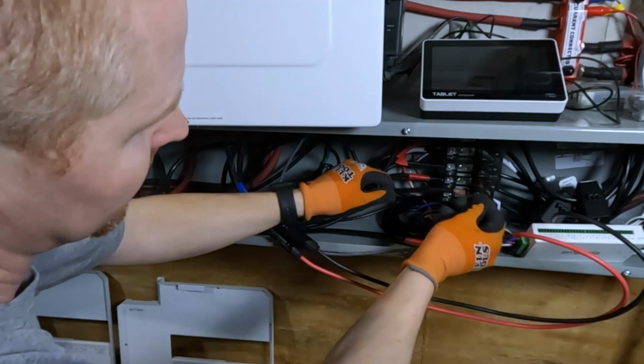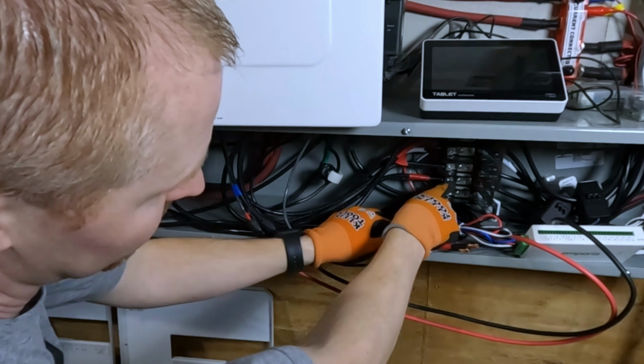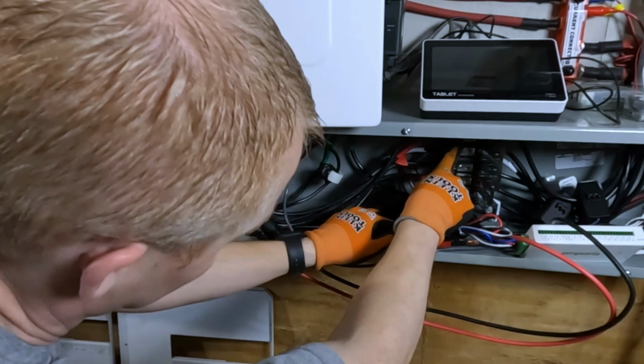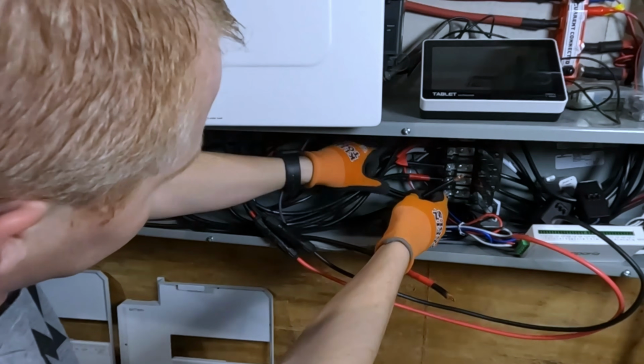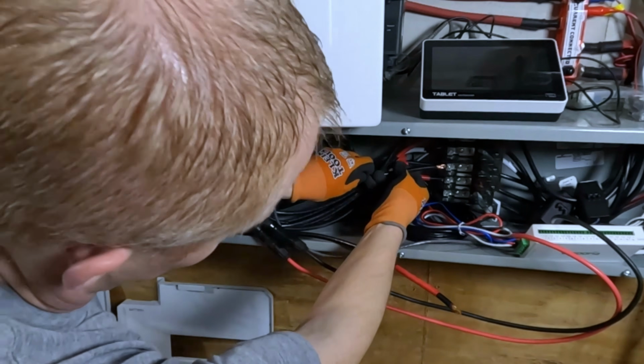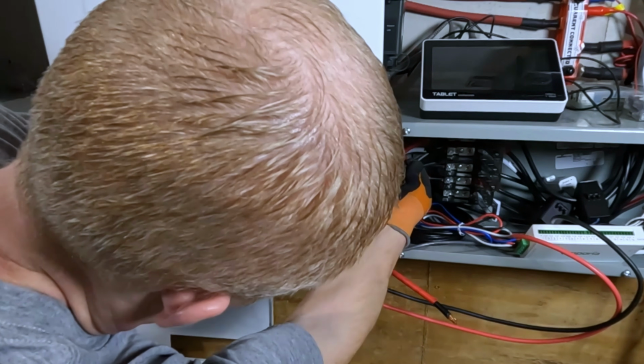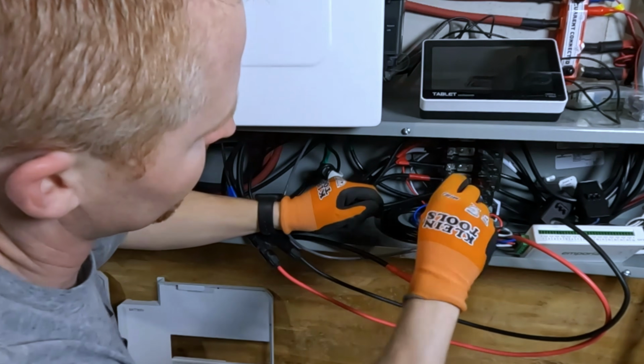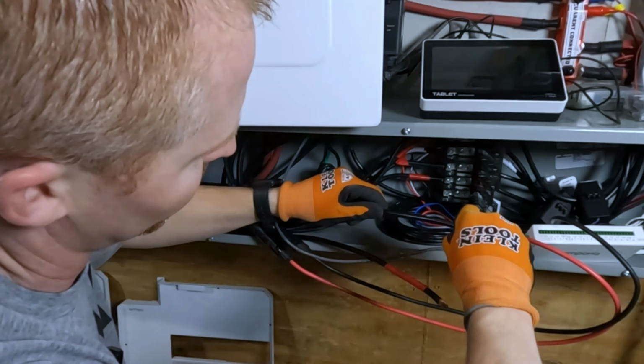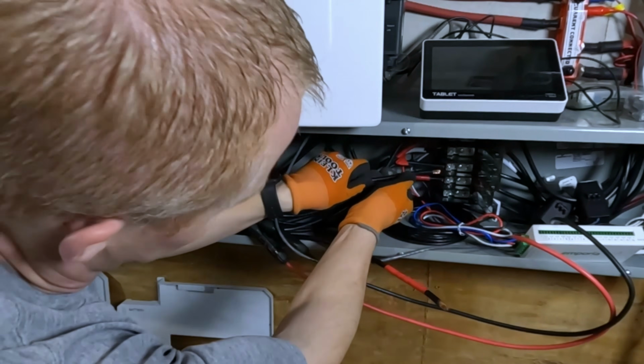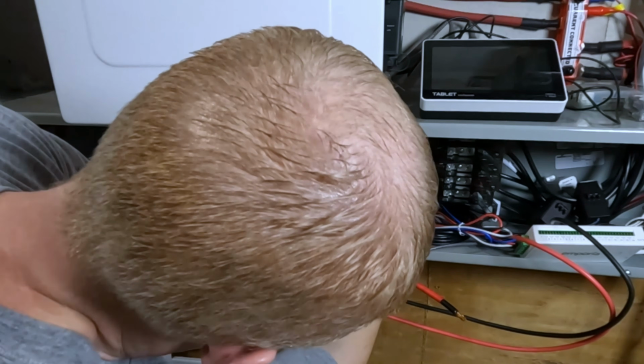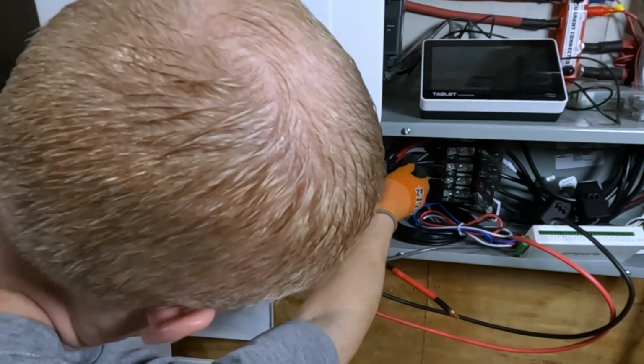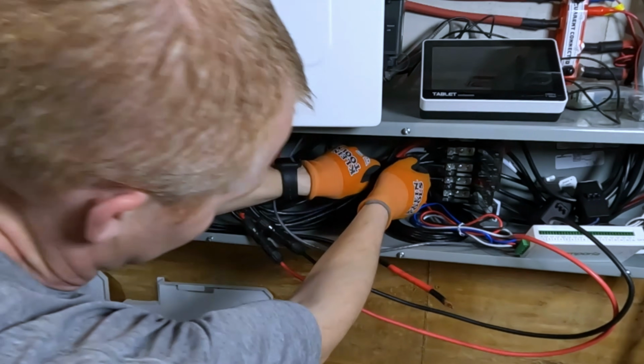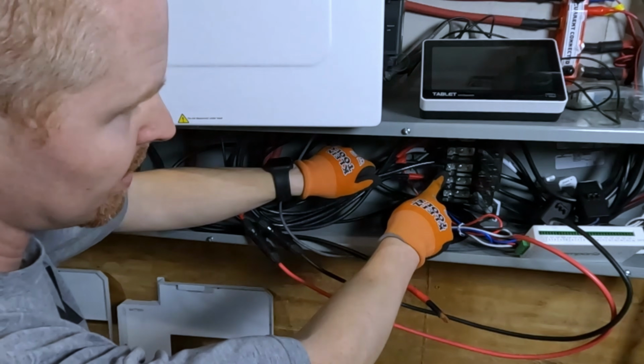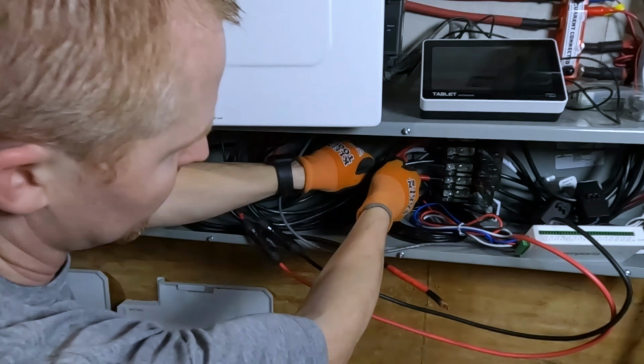So we've got our black line for output. The bottom PDB is my output. The top PDB is my input. So I'll run my leg 1 into, and remember this PDB is designed for 4 gauge is the largest that can go on this side. So it's very snug. So if you got 2 gauge, you would have to get a different size PDB.